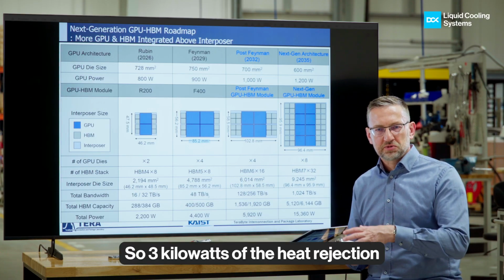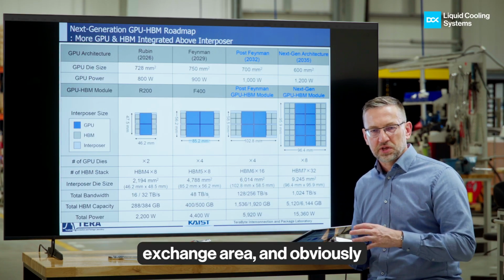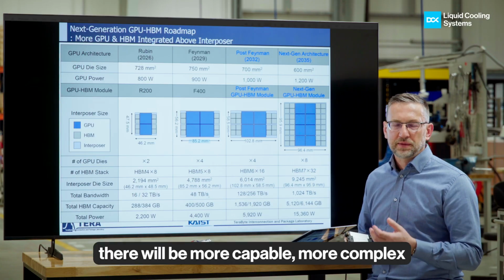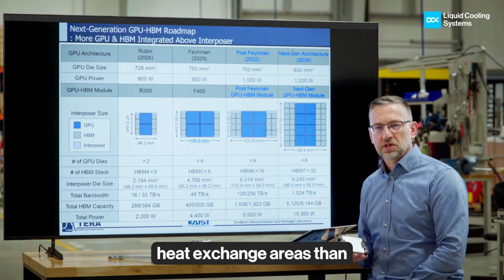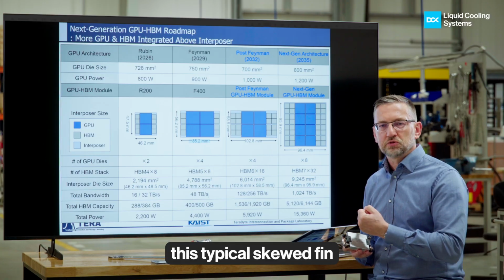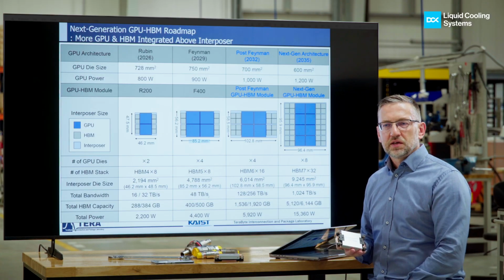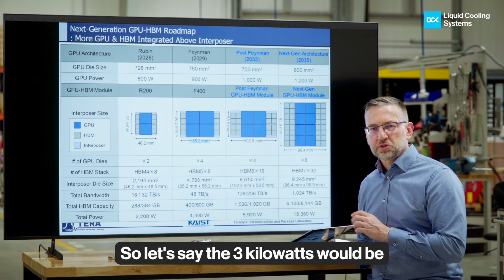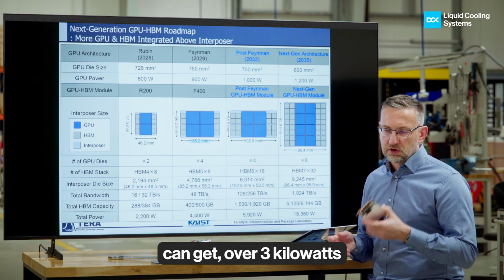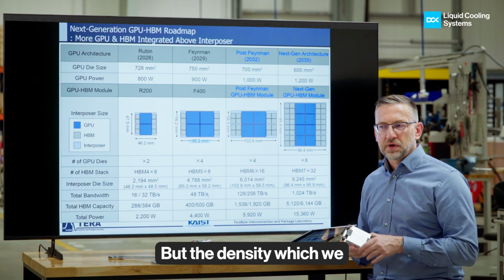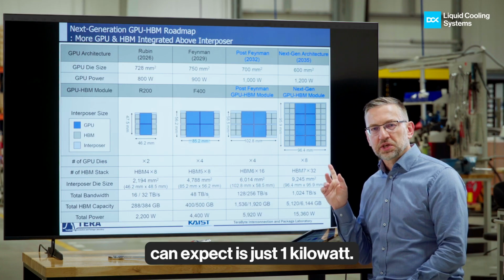3 kilowatts of heat rejection is possible from that heat exchange area, and there will be more capable, more complex heat exchange designs than this typical skived fin design. So 3 kilowatts, or a bit over, will be the maximum we can get, but the density we can expect is just 1 kilowatt.